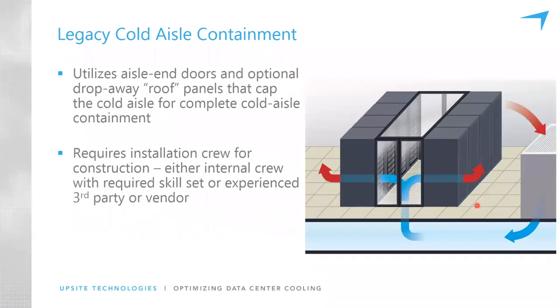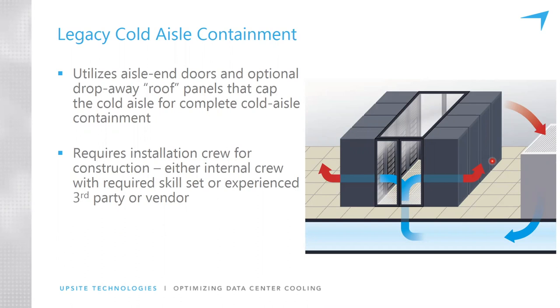With legacy cold aisle containment, the reason this generally isn't as efficient is that the rest of the room becomes hot. We're fully containing the cold air in the cold aisle, and when you open the door to a room with cold aisle containment done very well, it may be 90 or 100 degrees. A lot of people are not willing to work in that environment. While cold aisle containment is more popular because it's easier to deploy, it's often not done as well — meaning it's not fully optimized to its potential.